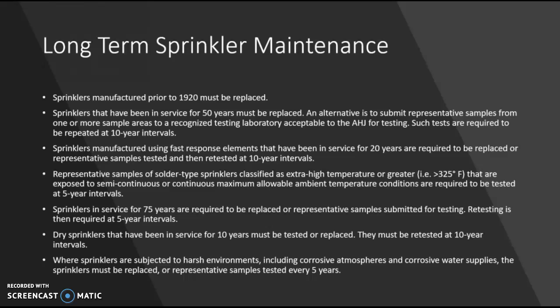So an alternative is to submit representative samples from one or more of the sampled areas to a laboratory and make sure that it's acceptable to the AHJ. They're required to be done every 10 years. Sprinklers manufactured using fast response elements that have been in service for 20 years are also required to be replaced. And naturally, I don't want to go through the whole list, but there's a lot of different methods and items that you have to go through with the older sprinklers, where you need to look through this list and actually make sure that your facility is up to date and correct in code.